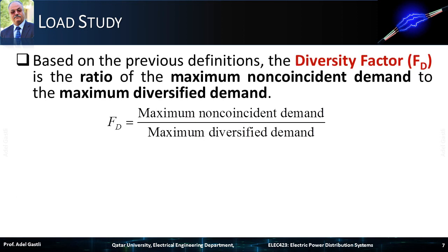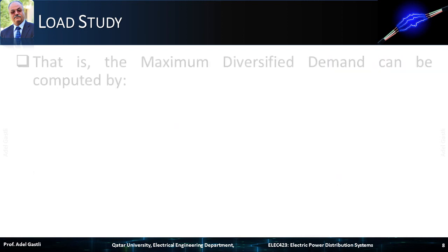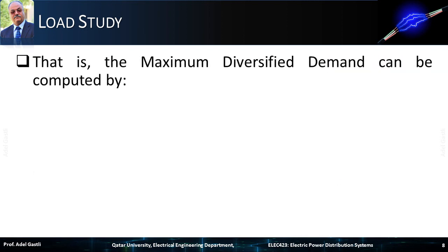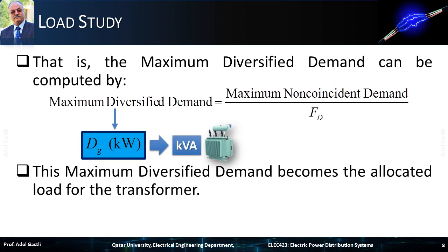Based on the previous definitions, the diversity factor FD is the ratio of the maximum non-coincident demand to the maximum diversified demand. When the diversity factor is available, it is possible to determine the maximum diversified demand of a group of customers, such as those served by a distribution transformer. The maximum diversified demand can be computed by calculating the ratio of the maximum non-coincident demand to the diversity factor. Hence, this maximum diversified demand becomes the allocated load for the transformer, after dividing the kilowatt demand by the average power factor of the total load.